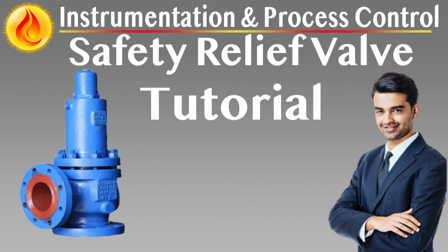Caution: use of non-balanced valves in systems where other valves may simultaneously relieve can increase back pressure beyond limits. Consider balanced or derated valves in such cases.